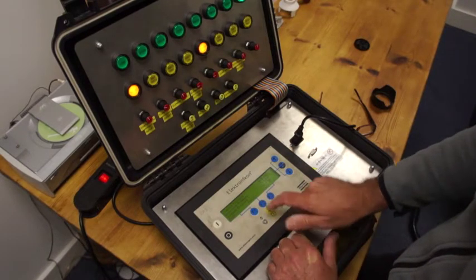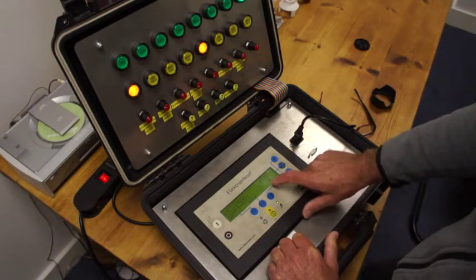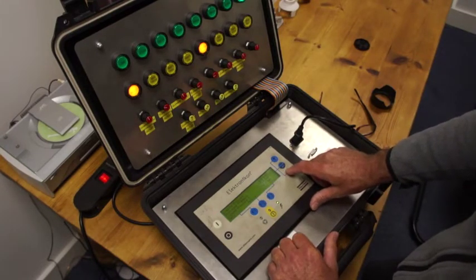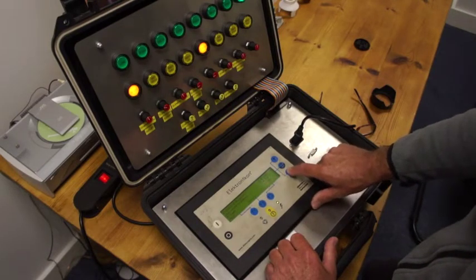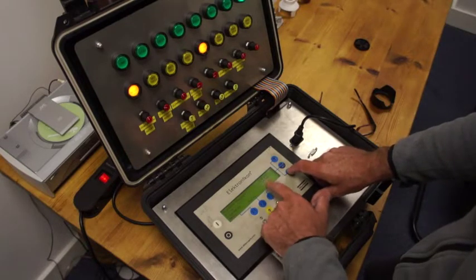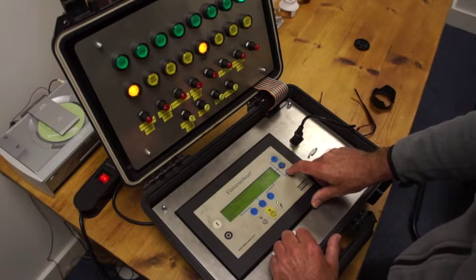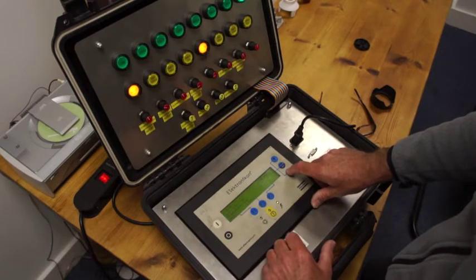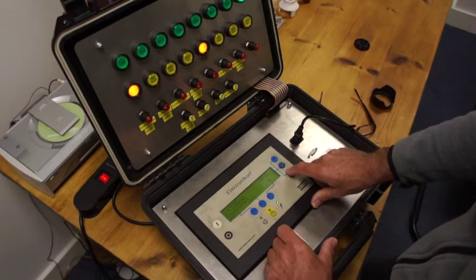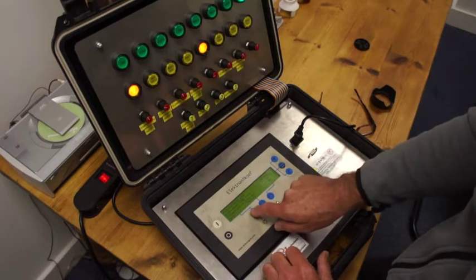We've programmed 7.3 bar. We've got loading pressure, unloading pressure, star-delta time — that's load delay time at 10 seconds — star-delta load delay at 12 seconds, number of starts per day set at 72, minimum stop time 20 seconds, and programming stop time. All these things you can modify but within limits. We're just going to go back now.